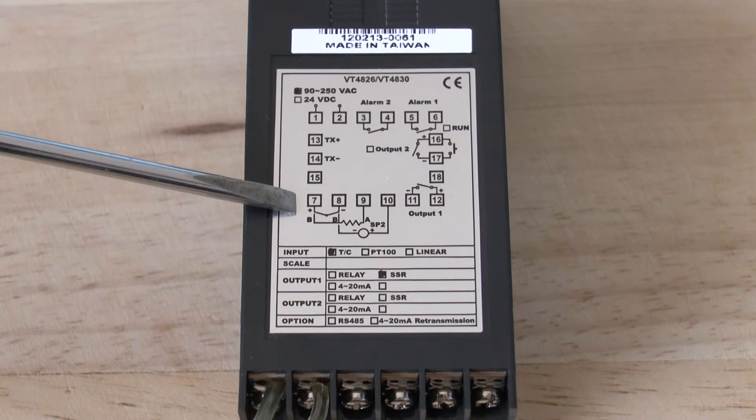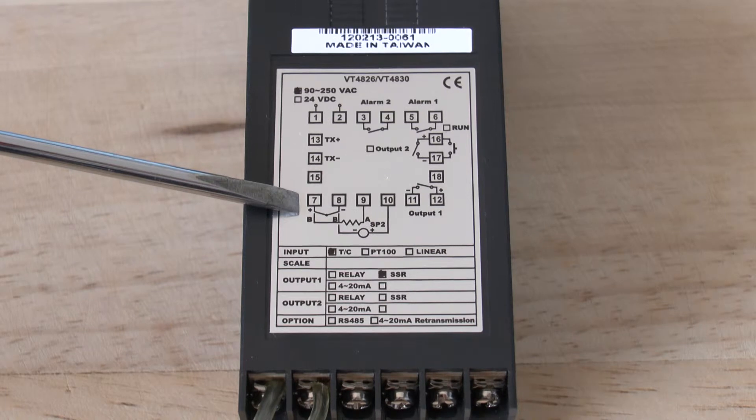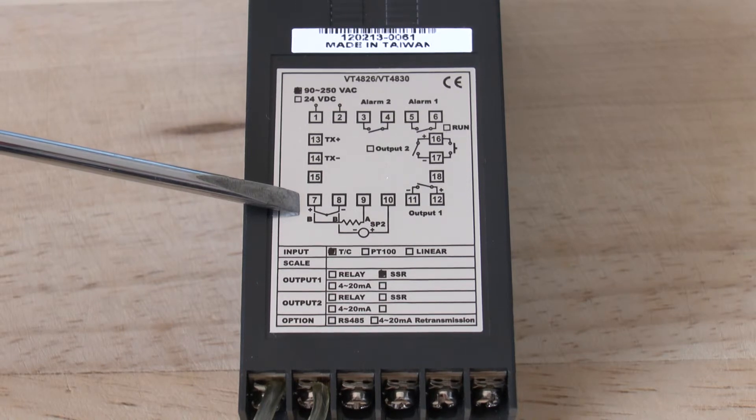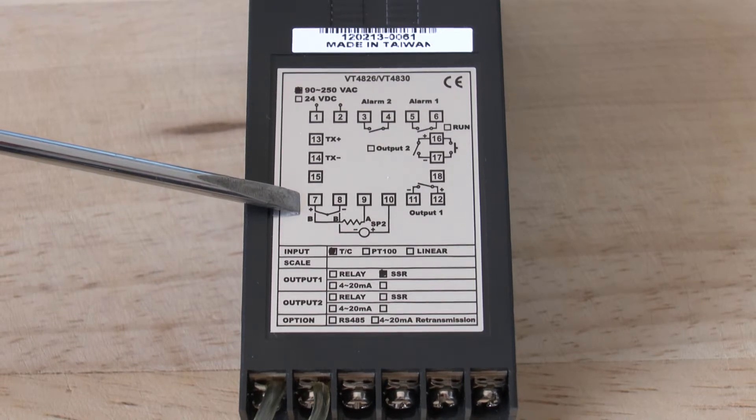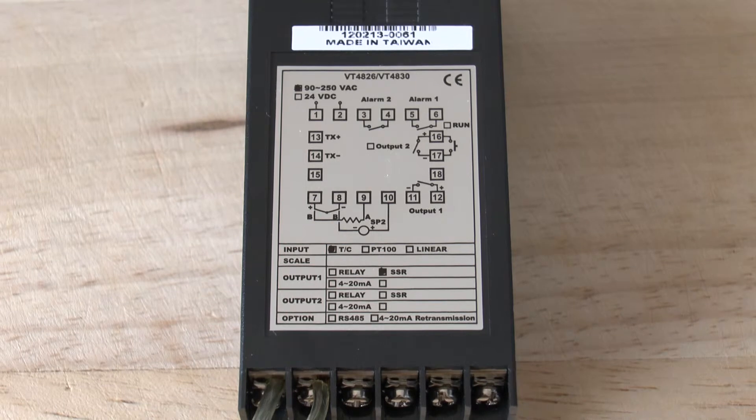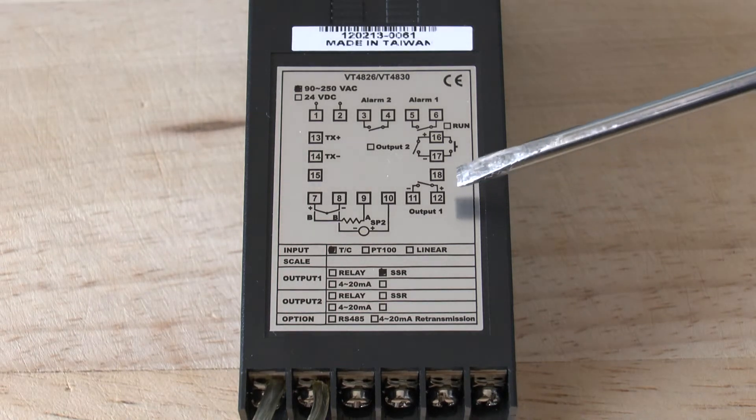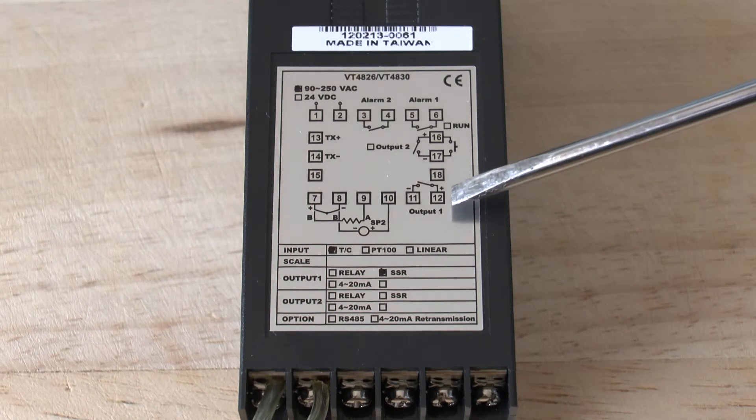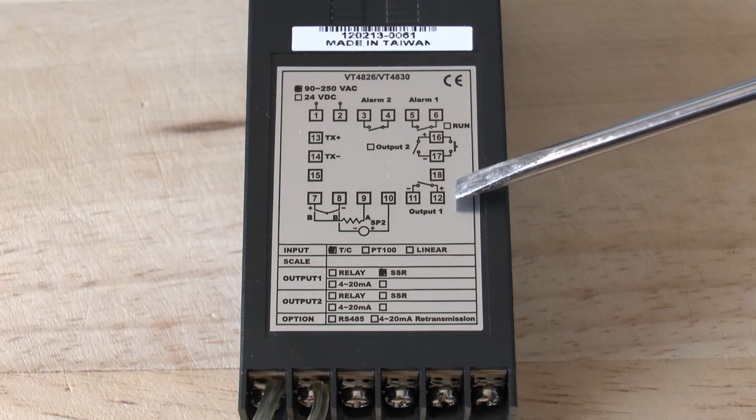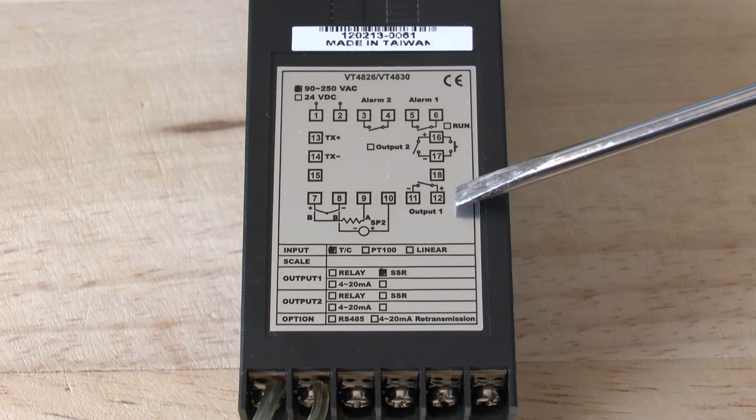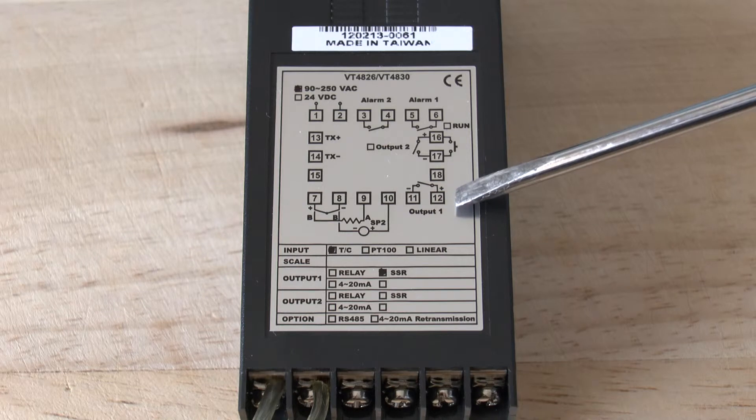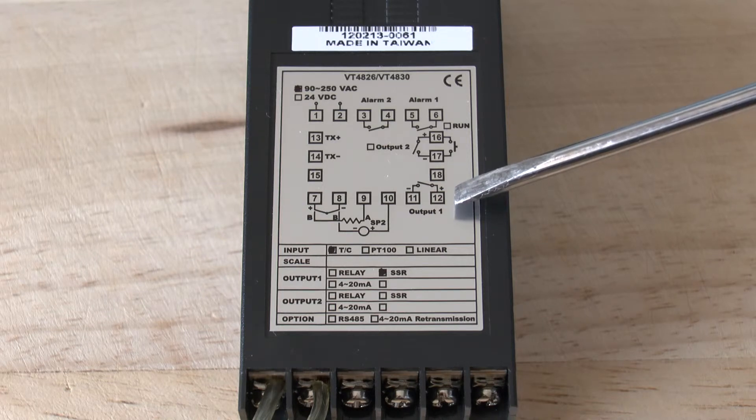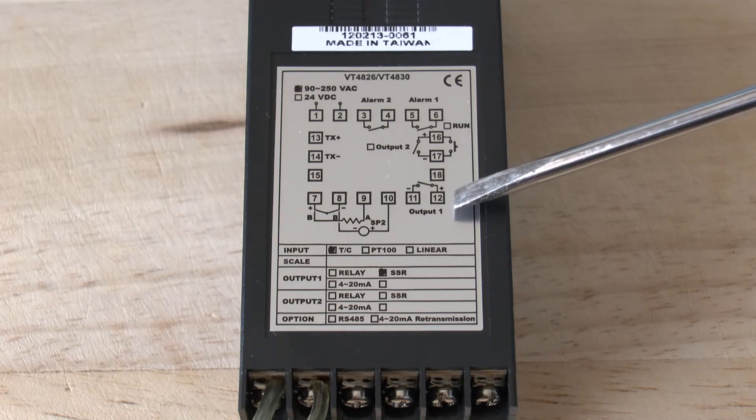On these controllers, the output is to be connected to terminals 11 and 12. The output can be either a relay output, in which case terminals 11 and 12 simply behave as a switch, switching a signal on and off, or it could be a solid state relay output.